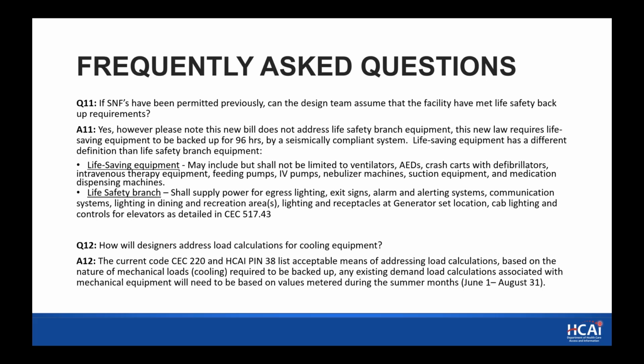And the life safety branch that we are all familiar with is used to supply power for egress lighting, exit signs, alarm and alerting systems, communication systems, lighting in dining and recreation areas, lighting and receptacles at generator set location, cab lighting, and controls for elevators. So it's a little bit confusing with the names so similar, but the life saving that's in this bill is completely separate from the requirements for life safety branch equipment. Question number 12.